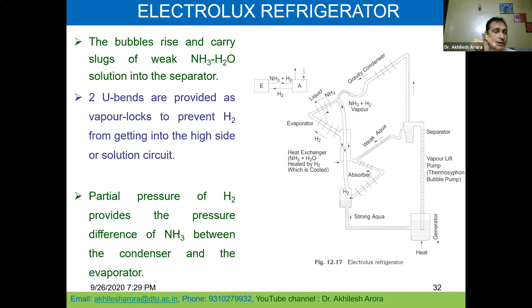If you look at the system here, you can see there is no expansion device. You remember the vapor compression system: after the condenser, there used to be an expansion device, an expansion valve, a throttle valve. Here there is no throttle valve at all. The function of the throttle valve is done with the help of the hydrogen gas already present in the evaporator, and it causes the pressure of ammonia to drop. By dropping the pressure of ammonia, the temperature also drops. So I hope this is clear to you.